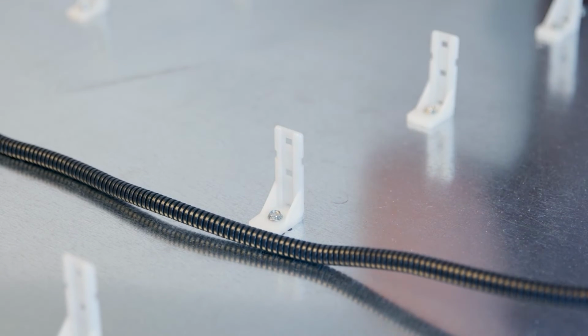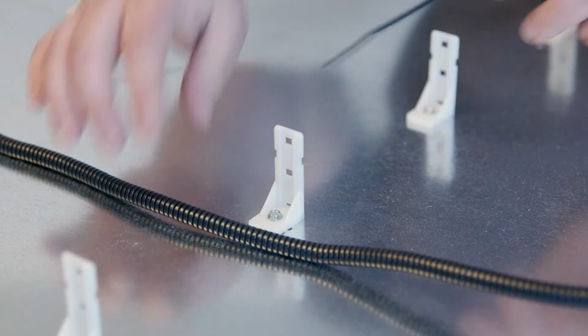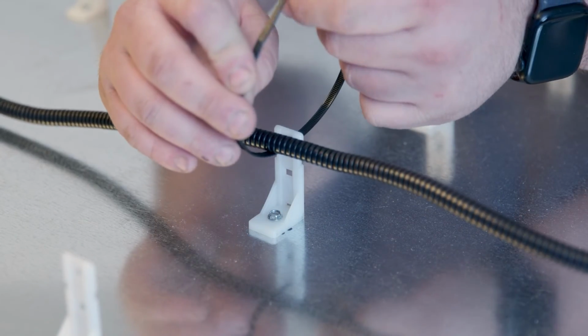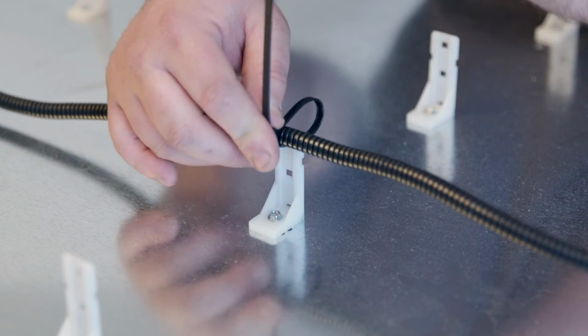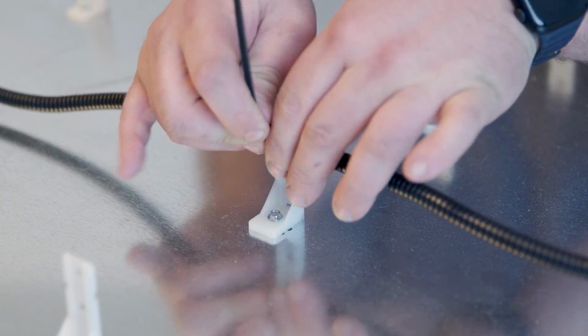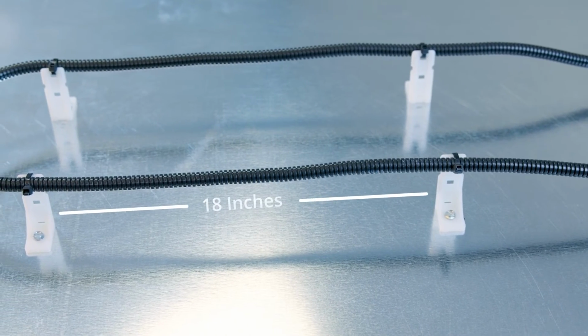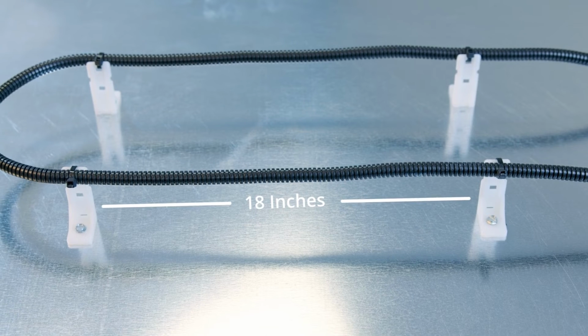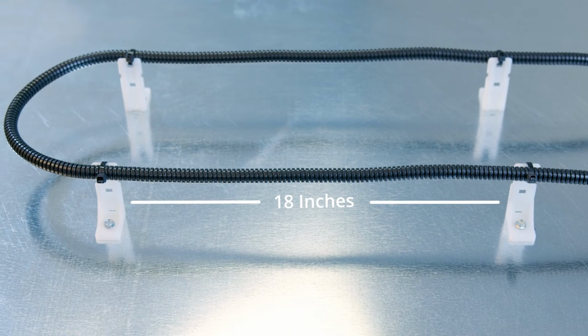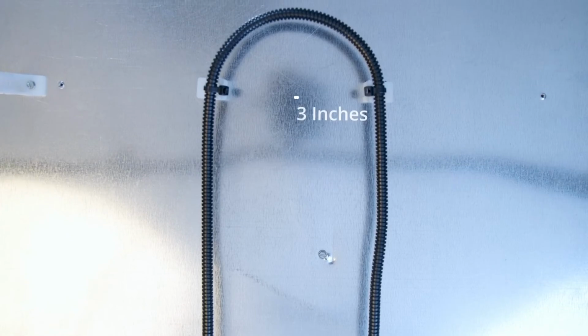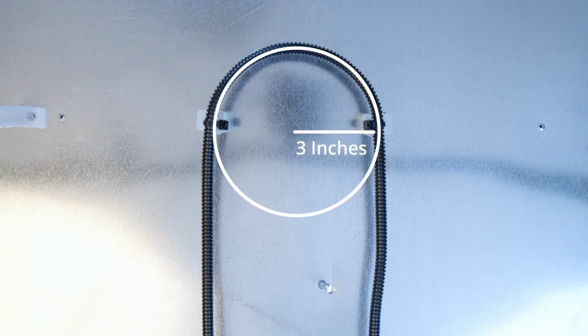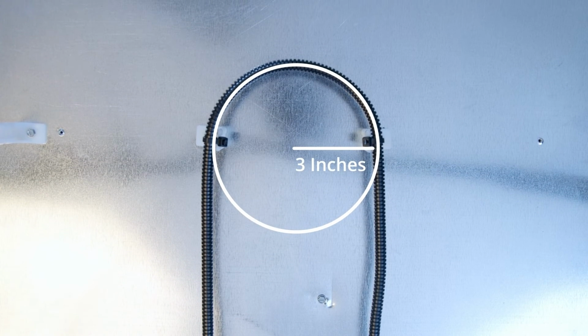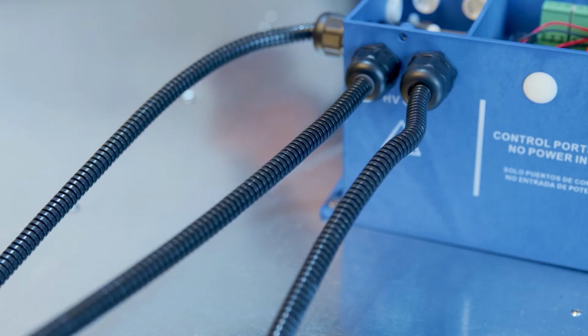Install the standoffs along the route of the high voltage cable. The cable should be supported such that it does not come into contact with metal at any point along its length. To prevent the high voltage cable from contacting a metallic surface, install the standoffs no further than 18 inches apart. Do not coil any excess cable. Instead, route any excess in a serpentine pattern and ensure that bends are smooth with a minimum 3-inch radius.